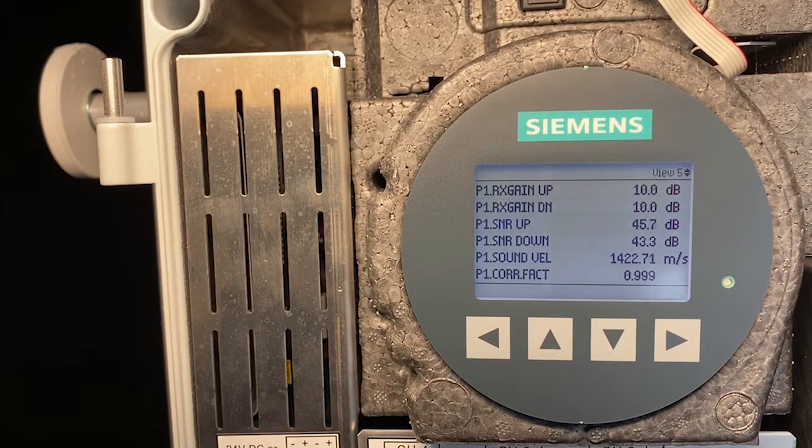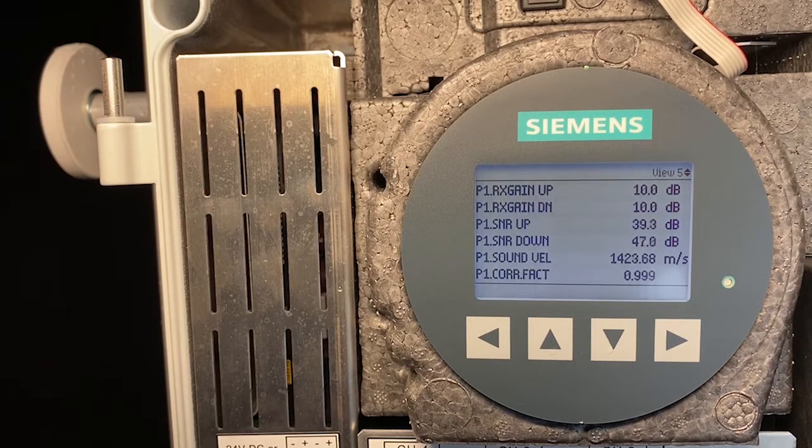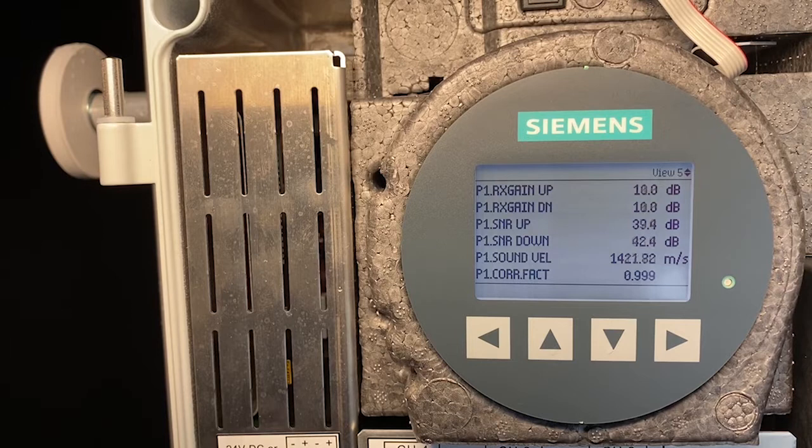View 5. We have the six diagnostic values. I let air in the tube and you can see the gain and signal-to-noise values are changing.